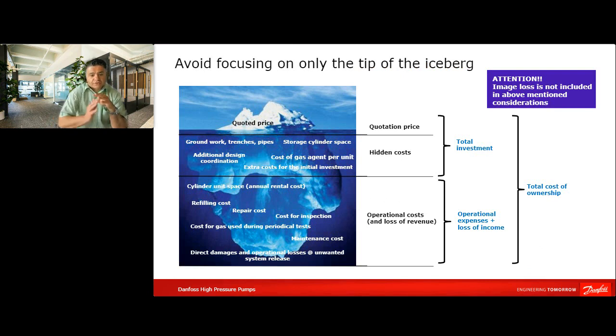What I would like to explain here, this slide is dedicated to when we compare high pressure water mist to a gas suppression system, but more or less the same is the case also when you look at a sprinkler system. As an operator, as an investor, if you get a quotation for a gas suppression system for a data center, and you compare it to the same with a high pressure water mist system, for sure, at first glance, the gas suppression system might be cheaper than a high pressure water mist.